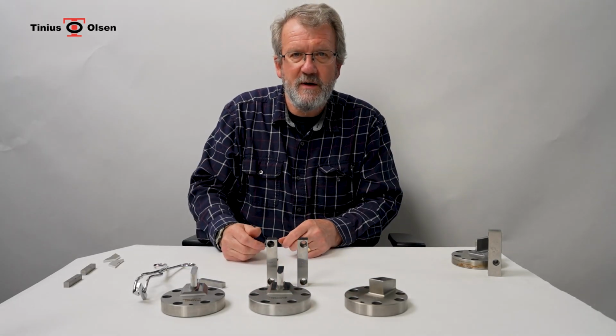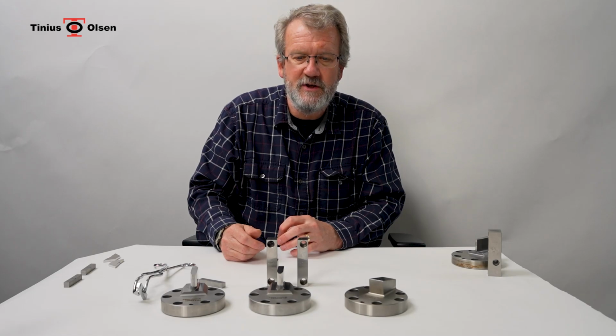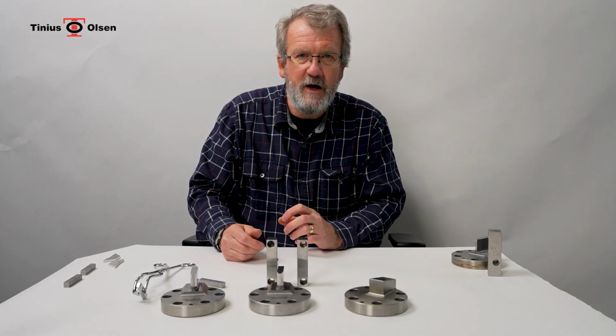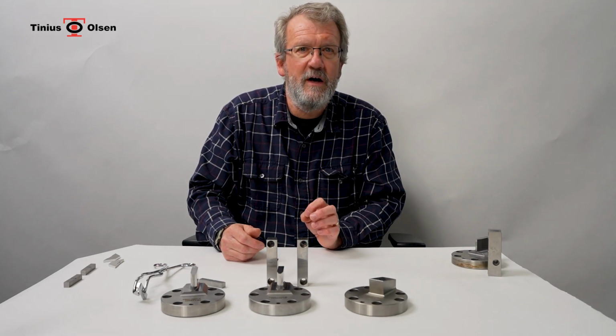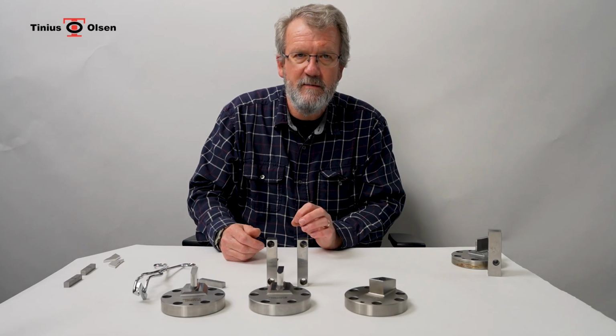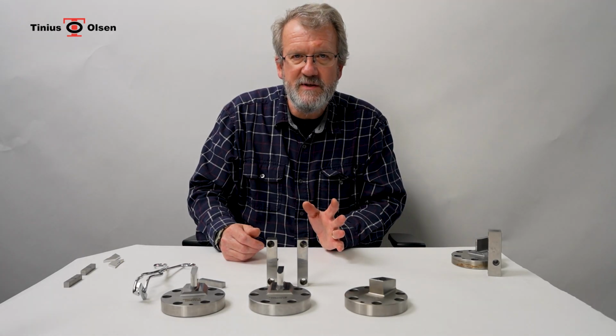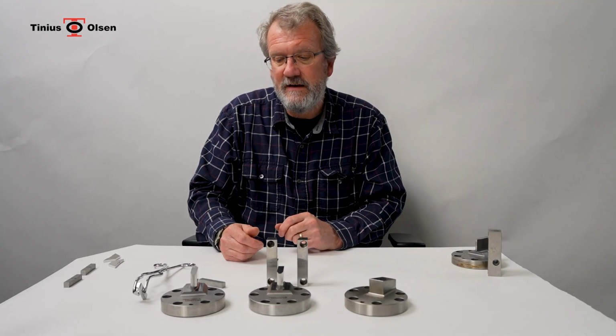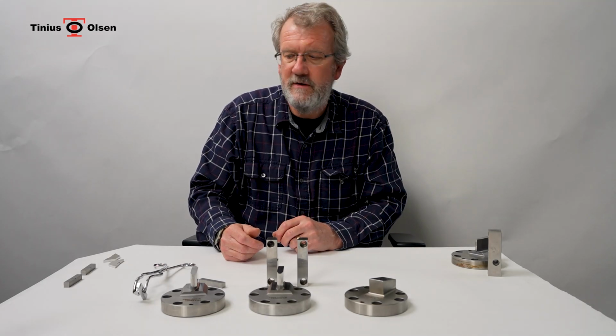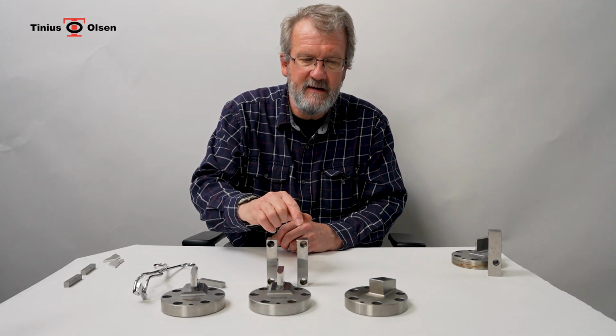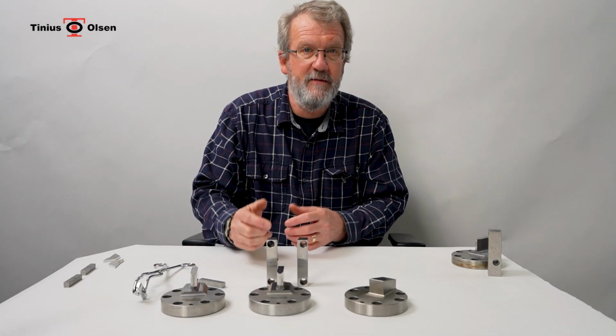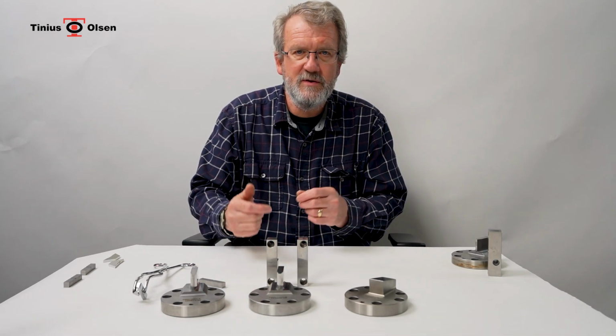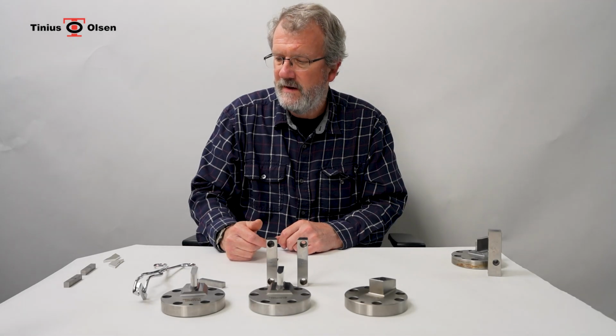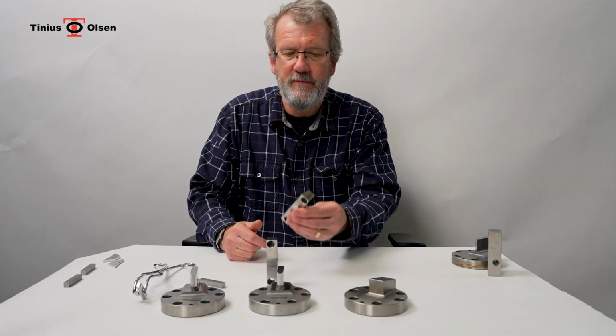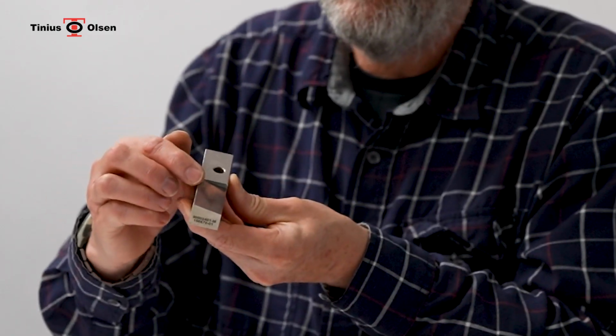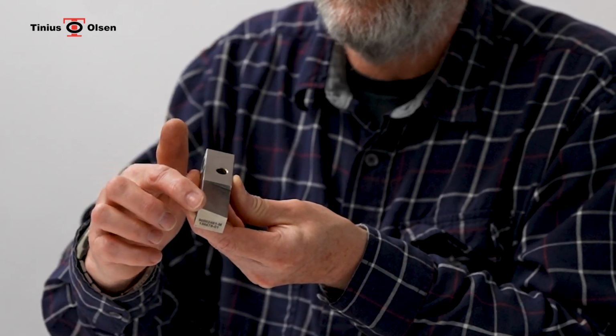So those are the basic components of the metal impact machine. One of the things that is required is an annual direct calibration of the machine. The ASTM E23 requires both direct and indirect. Direct verification monitors the spacing between the anvils, the radii of the various components, and the torque and level of the machine.